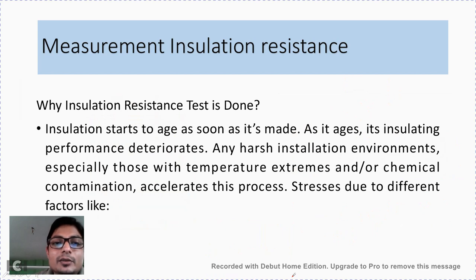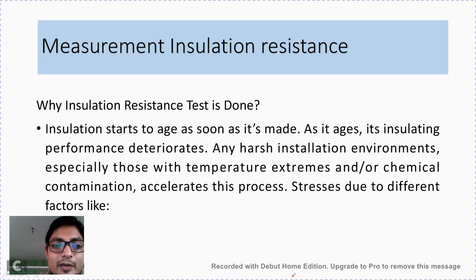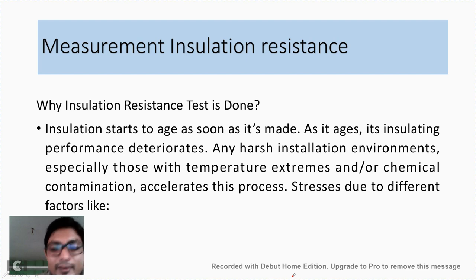Now let us see why we need to measure insulation resistance. Insulation starts to age as soon as it is made, and as it ages its insulating performance deteriorates. Harsh installation environments — especially those with temperature extremes, changes in voltage, or surrounding chemicals — may accelerate this deterioration. Therefore we must ensure the insulation resistance is at a proper level to maintain normal cable operation.